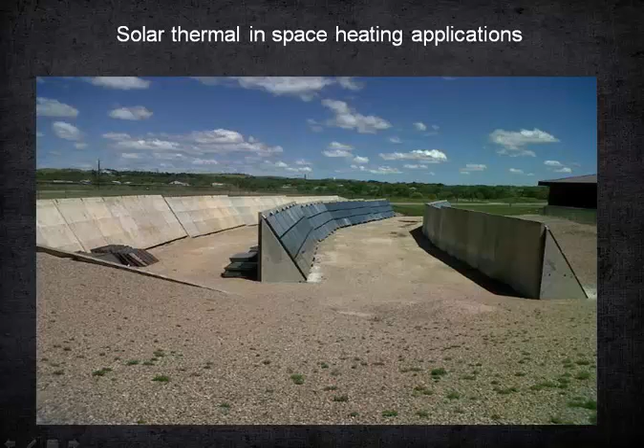So the challenges and valuation of solar thermal in space heating: we all know the source availability is opposite the load, and the capacity of the system is application-dependent. You can't just look at a collector and say it's good for X number of BTUs—it depends on how you're applying it as far as how many BTUs you'll get out of it. The valuation, or return on investment someone gets from that solar collector, comes down to how much work you'll get done with it, how much capacity it will have. The greater the delta T for the greater amount of time, the greater the capacity the solar collector can provide.